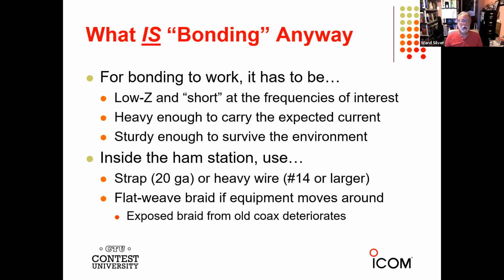Typically inside the station, that's not a problem. Outside the station, that can be a big problem because you're burying things and you tend to forget where they are. For example, if you have a buried grounding conductor outside, it has to be sturdy enough to survive when you rototill it up for the garden or dig it up with a shovel to put in a new tree or a bush. I don't think you have to ask how I know that. So if you don't use heavy enough stuff, you can cut right through it. It gets driven on, there are frost heaves, all these other things. It can break and you would never know that you don't have a ground connection anymore. That's one of the reasons why when you look at your building codes, it talks about number 6, number 8, number 4, big, heavy stuff.